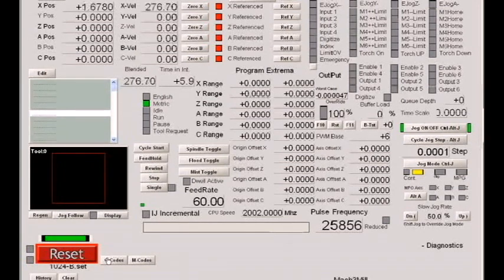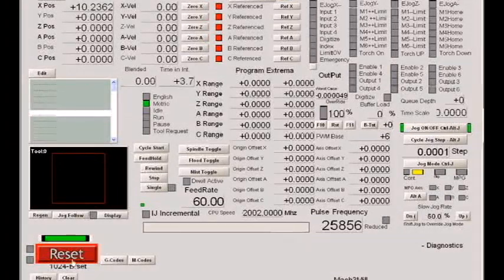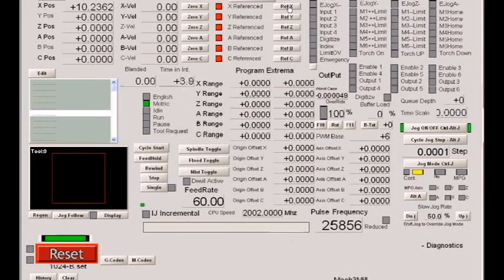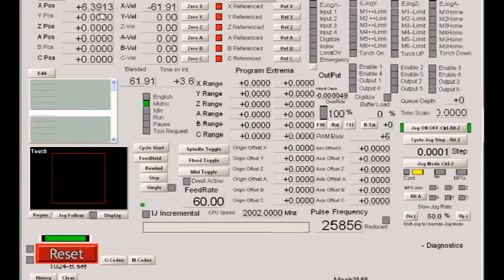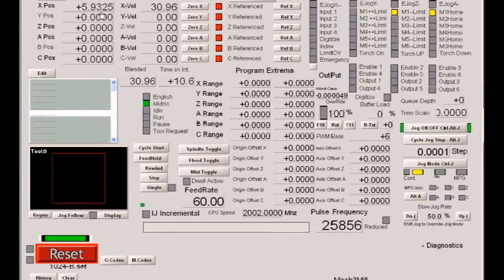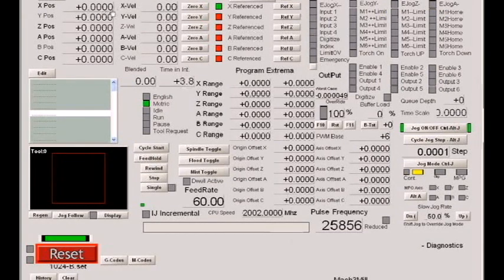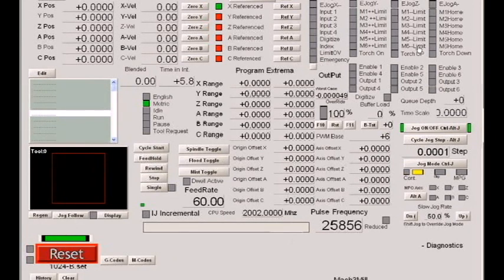Now let's say by chance that we drive away from the switch and we hit reference X. The axis now moves towards the switch, and when it hits the switch, it immediately reverses direction until the switch comes off, zeroes our displays, and the switch now becomes a limit switch again because we're no longer referencing.